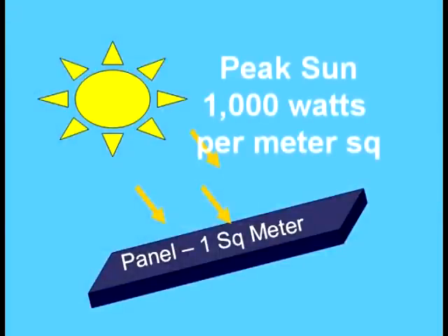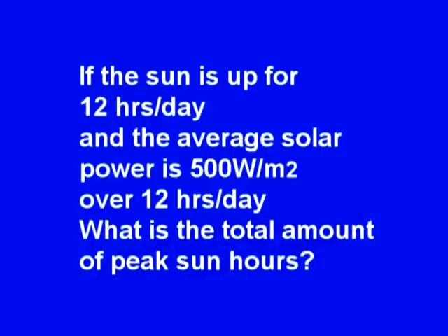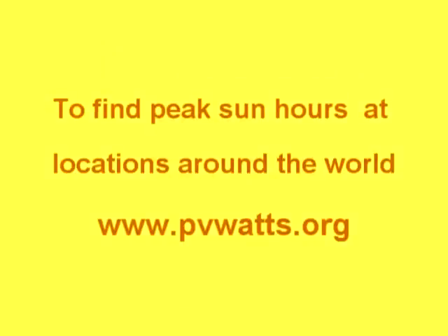We get a thousand watts per square meter, and coincidentally this is what they use for the rating conditions. Every nameplate rating on the back of the modules is based on this thousand watts per square meter solar radiation level. So if the sun is up for twelve hours a day and the average solar power is 500 watts per square meter over twelve hours, the total amount of peak sun hours equivalent would be six — six kilowatt hours per square meter. There are internet sites to look up peak sun hours in locations around the world.